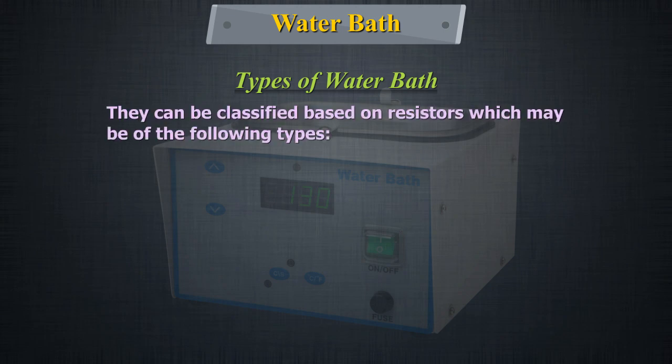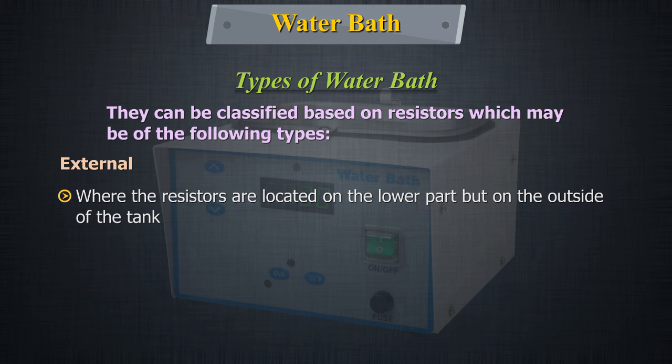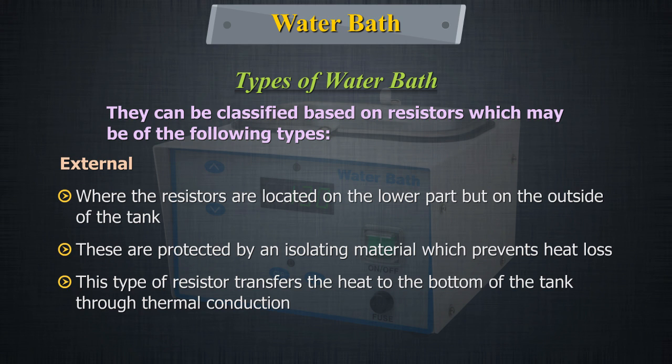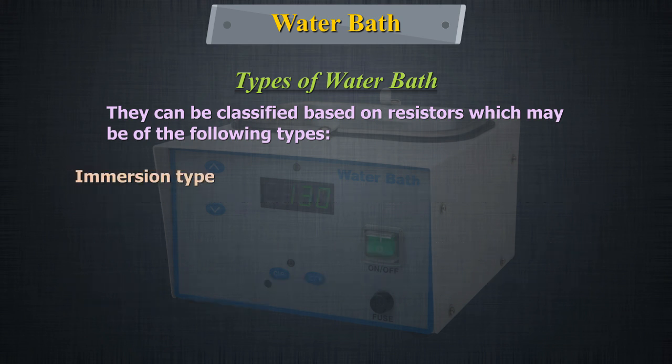Water baths can be classified based on resistors, which may be of the following types. In one type, the resistors are located on the lower part but on the outside of the tank. These are protected by an isolating material which prevents heat loss. This type of resistor transfers heat to the bottom of the tank through thermal conduction.